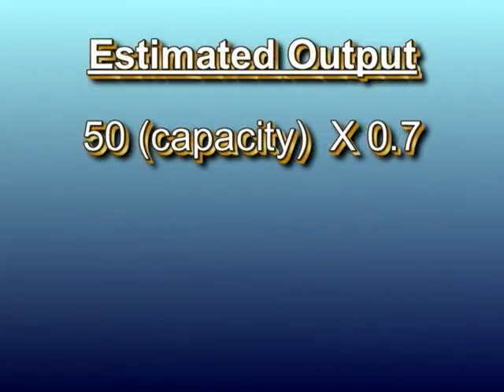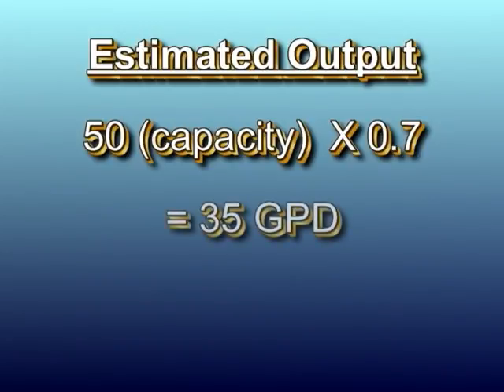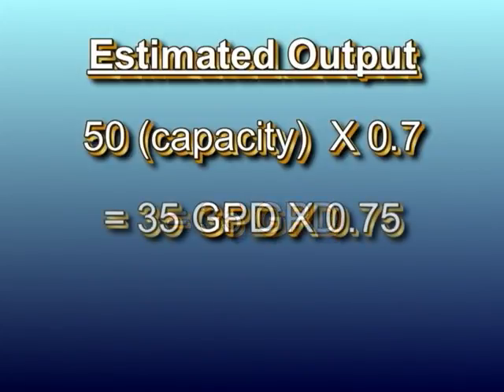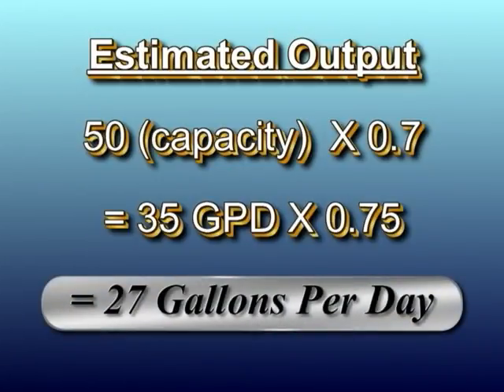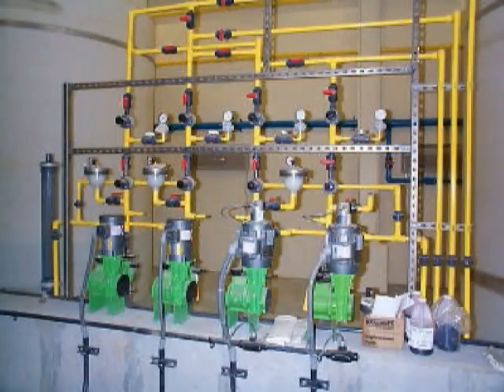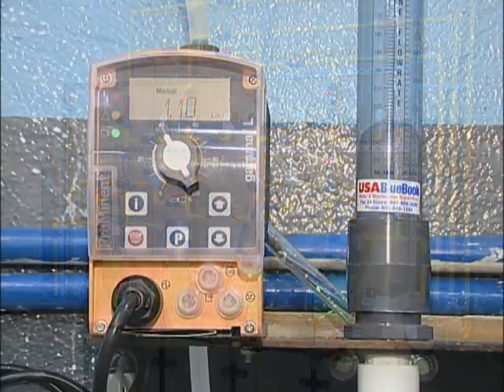To get this estimate, the maximum output of 50 gallons per day is multiplied by the speed setting of 0.70, yielding 35 gallons per day. Then by the stroke setting of 75, which gives about 27 gallons per day. Regardless of whether the manufacturer suggests this method or not, the best way to determine the efficiency of a pump is to do a pump calibration.